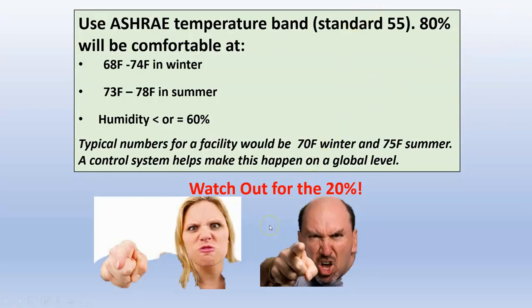And when they say 80% of all people will be comfortable, based on all my experience and everybody else I've talked to, I believe that 80% of the people will be comfortable at those temperatures, especially if you keep the humidity at 60 or below. But that 20% can be extremely nasty, and a lot of times they'll override the other 80. So that's just something you've got to be prepared for.